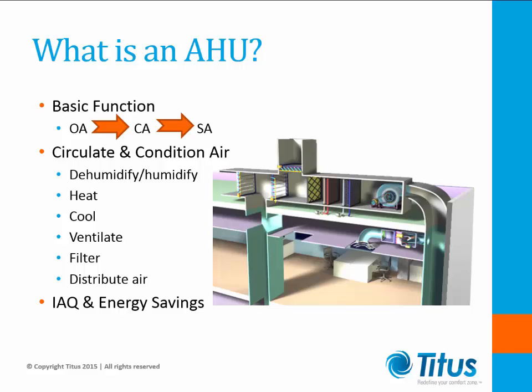Let's ask ourselves a simple question. What is an AHU? The basic function of an AHU is to take in outside air, recondition it, and supply it back to the building. All exhaust air is removed, which creates an acceptable indoor air quality. Depending on the room temperature of the reconditioned air, the fresh air is either heated by a recovery unit, a heating coil, or cooled by a cooling coil.